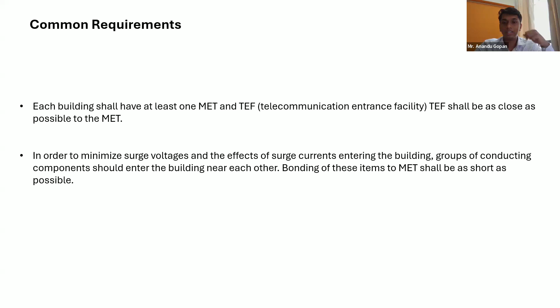If you see your lightning protection standard also, each and every zone will have a surge protective device, to control the surges going into the other zone. So at the entrance, you have to have an MET, and you are going to reduce the surges entering your building. Maybe you can use an SPD, you can use your data SPDs, all of these things to interconnect. These systems can be cables, armoring of these signal cables, even power cable armoring, and it can be anything. And then you have your common requirements for these in the upcoming slides.